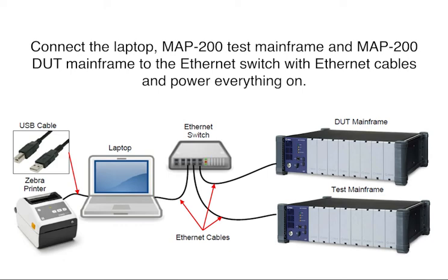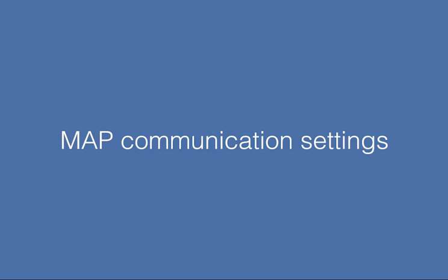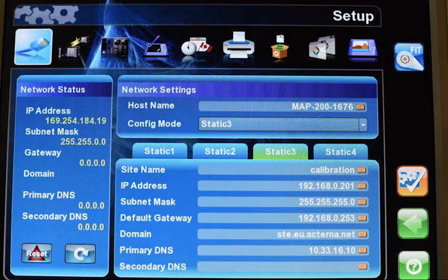The FOPLT software that controls the calibration process runs on the laptop supplied with the kit. Start it up. First, we may need to update MAP's communication settings. At this MAP 200 setup screen, in Network Settings, select Static 3 for the configuration mode. In Network Status section, change the IP address to 192.168.0.201 and update the subnet mask to 255.255.255.0. Finally, click the orange button to accept these changes.